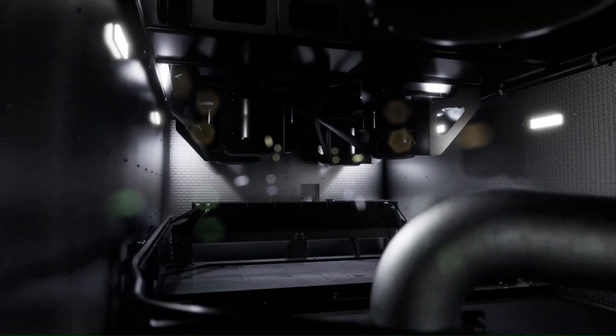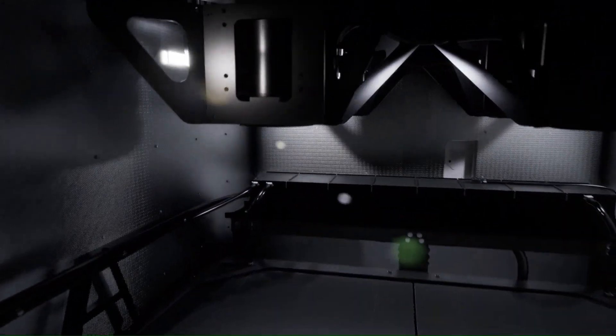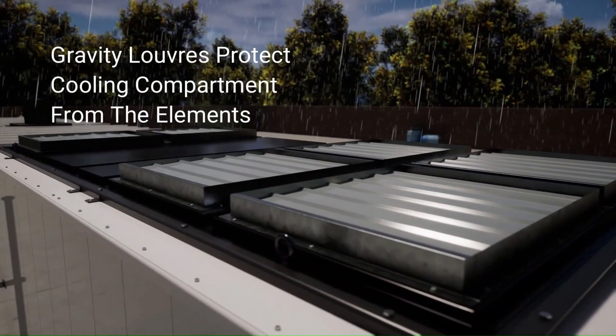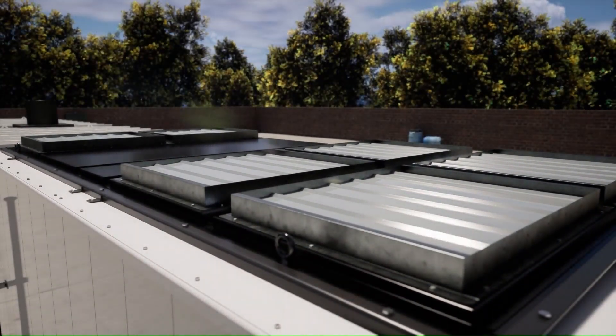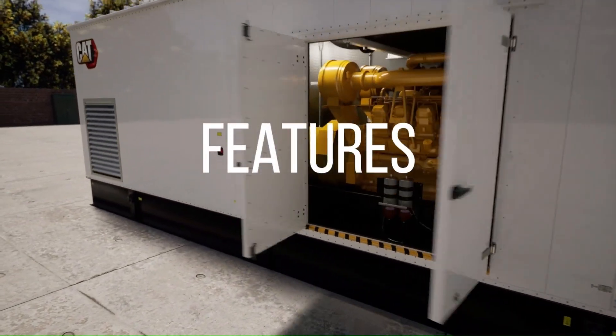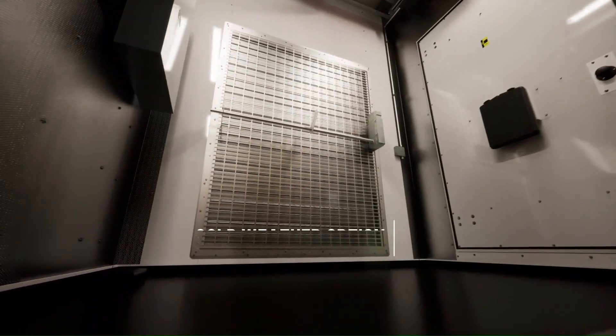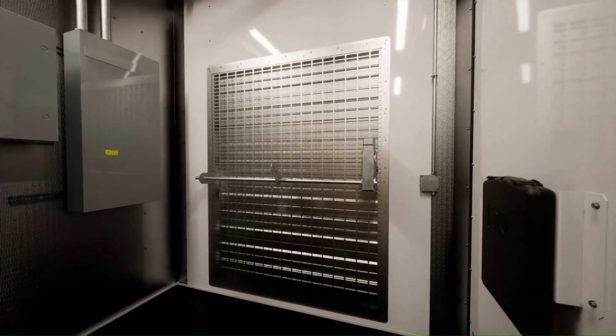As we move back up toward the roof, you can see the electric motors driving the cooling fans. Gravity control of the louvers means they automatically close when the generator set is switched off, thus protecting the cooling system compartment from the elements. Some of the features of these enclosures include a cold weather option which incorporates motorized intake louvers and a 5-kilowatt electric heater.